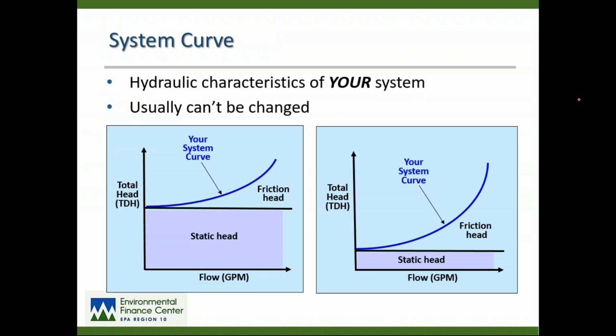Okay, you should know a little bit about your system curve, and your water system or even your wastewater system has its own system curve. This is something that the operator can't change. The system curve is basically the relationship between friction head and static head. This chart, or the illustration on the left, is a good example of a system where as soon as the pump starts, it has to lift water high up a hillside. So the proportion of static head to friction head is much greater if you're lifting water a great distance vertically. The minute that pump starts, it is already fighting a lot of static head.